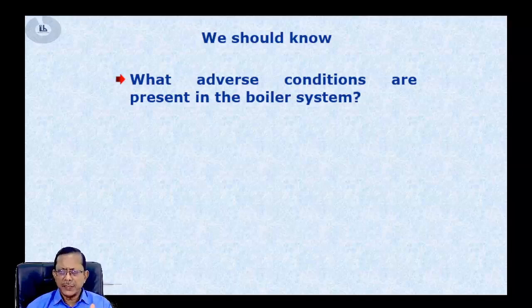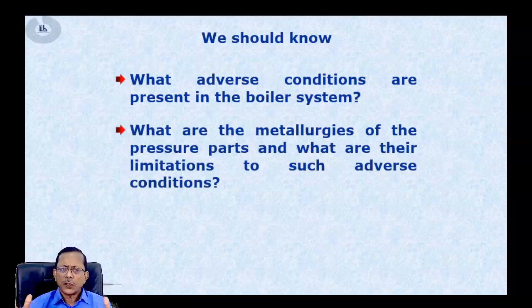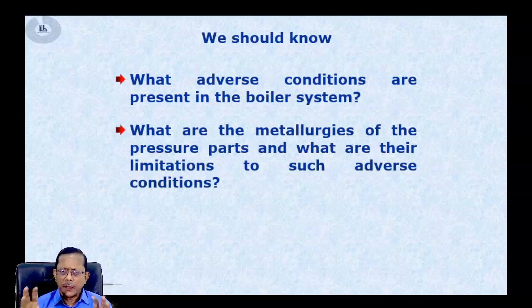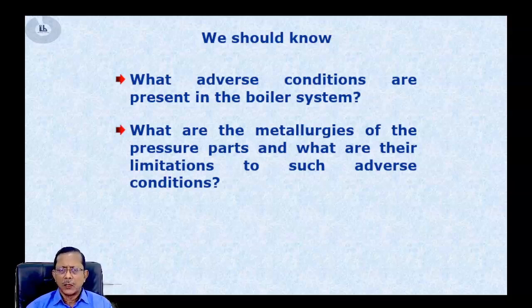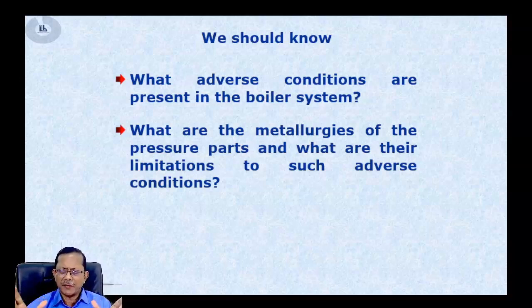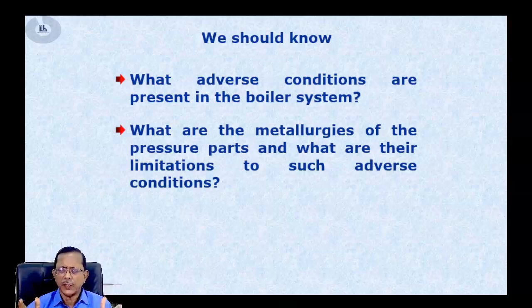We should also know what metallurgy is used in the boiler components and, most importantly, the limitations of that metallurgy. A very common myth: since steel is used for all tubes, and we know steel is very strong, we tend to feel that steel can handle many adverse conditions. That is a complete myth. Boilers work with metallurgy that barely has the capacity to withstand the conditions under which it operates. This understanding must be thoroughly present with every operations, maintenance, and inspection engineer.